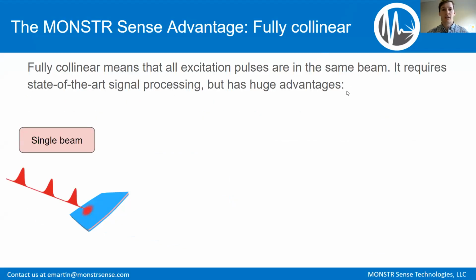Now, what makes our ultrafast spectrometer special is that, unlike our competitors, it is fully collinear. Fully collinear means that all the excitation pulses are in the same beam. This requires state-of-the-art signal processing, but really comes with some huge advantages. So the single beam has the primary advantage that it is compatible with microscopy. Conventional ultrafast spectroscopies have pulses in different beams, meaning that the beams have to cross in the sample, right? So they are a non-collinear type of technique. This is not compatible with using a microscope objective.